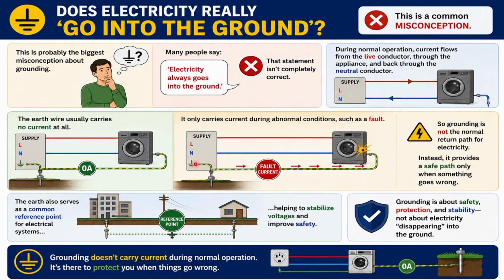But current actually goes to the ground only where we have a fault, right? Let's say electricity flows into the appliance and there is broken insulation inside the appliance, and when that happens, electricity probably gets in contact with the body of the appliance. In this case, that leakage current, due to the failure of the insulation, is what is going to flow directly to earth. So grounding is not a normal return path for electricity. Instead, it provides a safe path only when something goes wrong. So mainly grounding is for safety, protection, and stability, not about disappearing electricity into the ground. Grounding doesn't carry current during normal operation. It is there to protect when things go wrong.